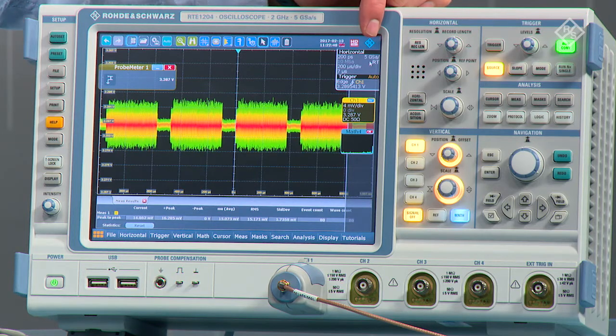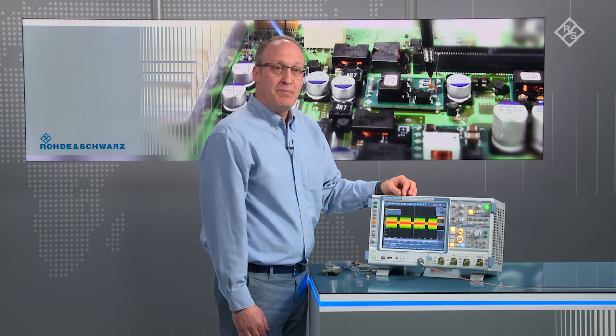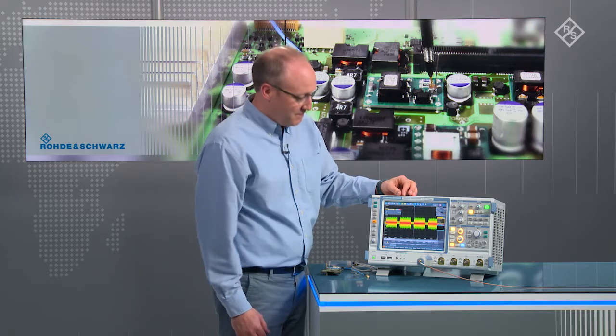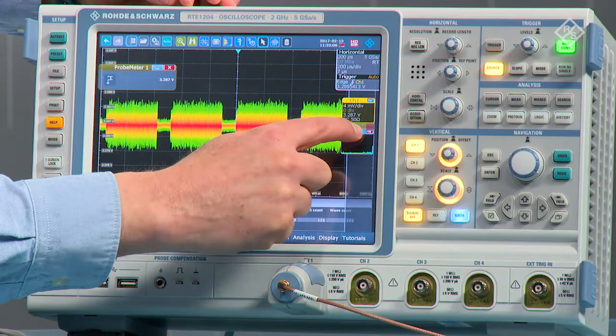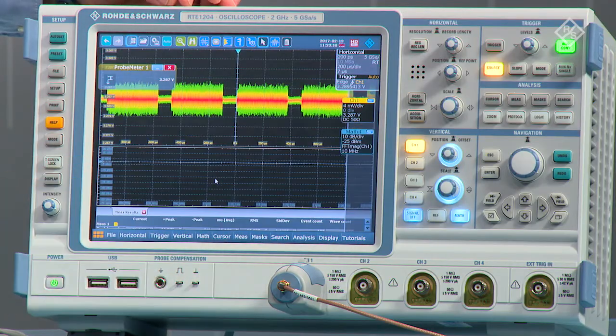Power integrity measurements often require longer time captures with fast sample rates. Here we can see that we're using 10 megasamples of memory. Notice that the scope stays responsive. With electronic PCB miniaturization, coupling of nearby sources on the power rail, such as fast clocks or other signals, present a higher risk.